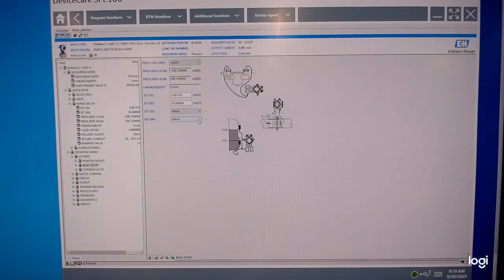Okay, now this trickier one is right here, the get URV. This is where I have to pump up my hand calibrator up to the upper range that I would want to set this up for. And so what I need to do is plug the line in, and I'm going to go ahead and pump this thing up to 50 inches of water here. Everything goes well. Back this down a little bit. So I didn't go too far already.